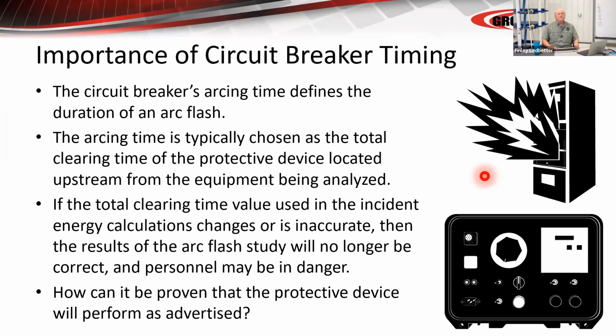Circuit breakers arcing time defines the duration of the arc flash. Total clearing times, very important. It's not just parting time. It's not the time you get from a simple timer. Realize that. It's a bigger number than that. The total clearing time value used in the incident energy calculations are very important to ensure that your PPE is correct. How can it be proven that the protective device will perform as advertised? Timing is really the best tool you've got to do that.